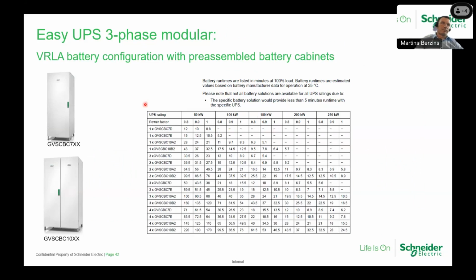Regarding the valve-regulated batteries, we have these pre-configured battery cabinets available for delivery and installation. So the batteries are already inside, and the battery breaker kit is already installed inside the cabinet. So very easy to deploy, bring on site, and connect to the UPS. Quite a simple approach to get batteries. We have information on how many runtime minutes each battery cabinet can supply for each load. If you notice that these battery cabinets are white in color and the UPS itself is black.